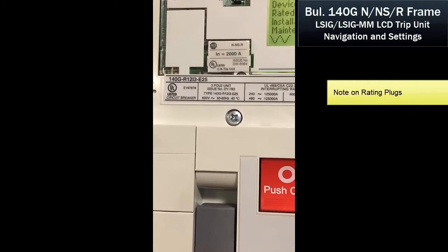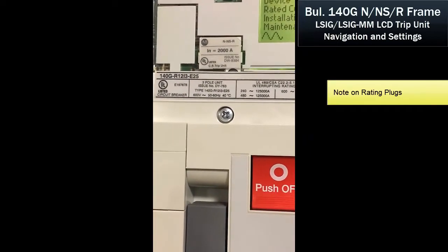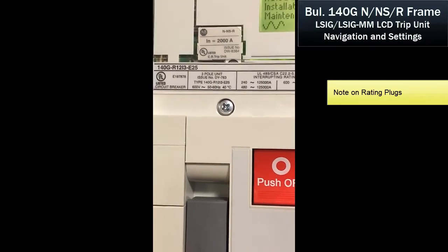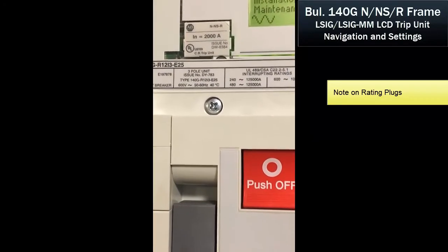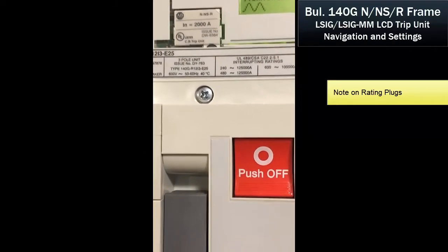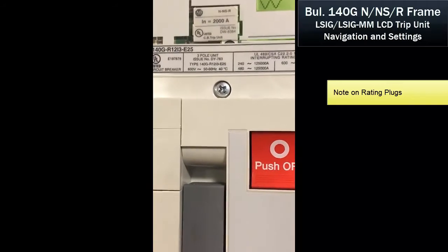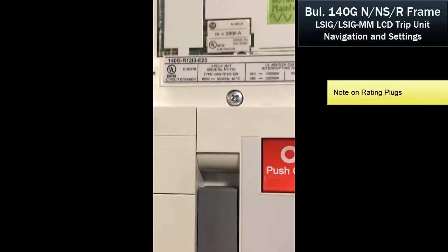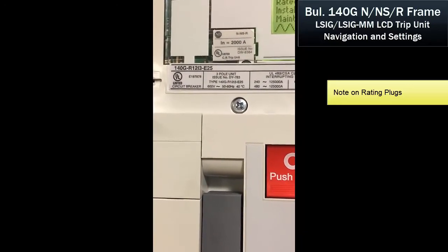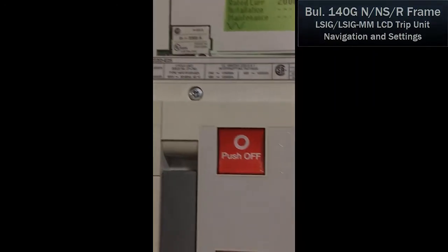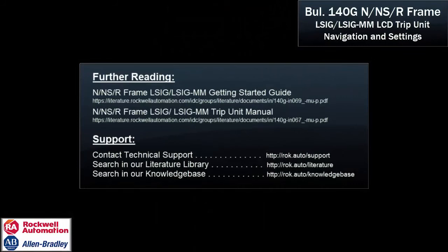The thing to note on these breakers is that you can put rating plugs in, and the rated current value will change. You could put an 1800 or 1600-amp rating plug in there and change the rating of the breaker. In this particular breaker, you could put up to a 2500-amp rating plug — this is a 2500-amp MCCB. That takes us through the setup and display portion of the menu. If you have any questions, please let us know. Thank you.